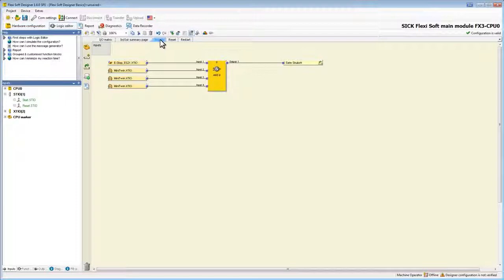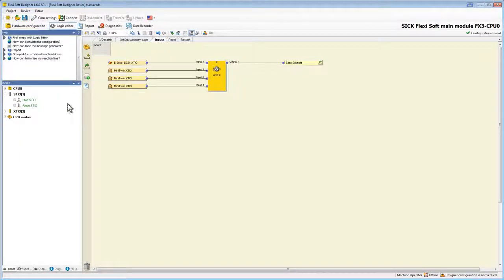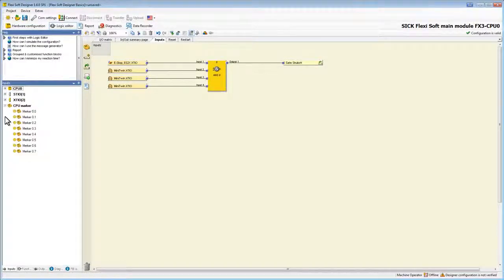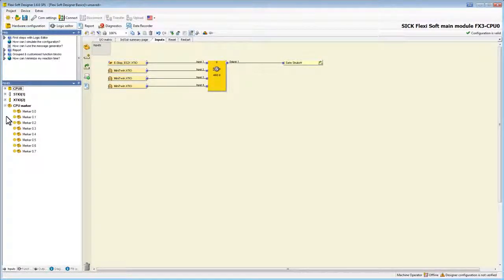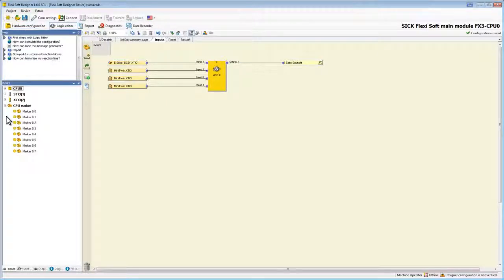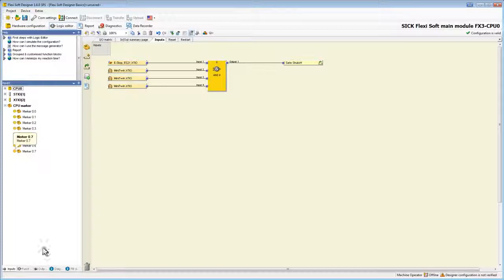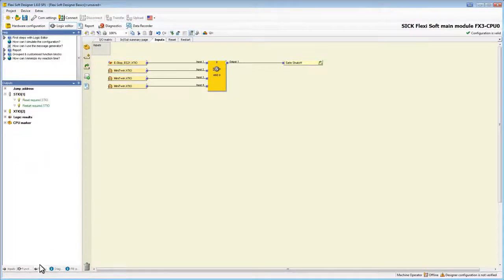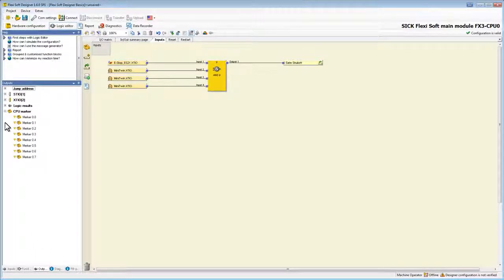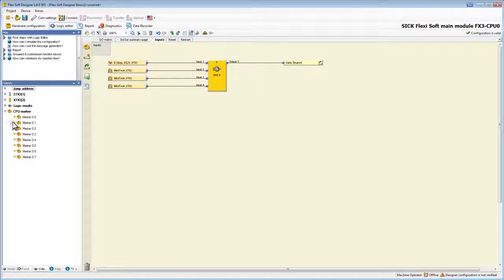The use of CPU markers works basically in the same way as the jump addresses. CPU markers are available as in and outputs here, and contrary to the jump addresses there is always a delay of one logic execution time between the output marker and the input marker. The CPU markers can be considered as variables which are readable and writable. Therefore they are available for gateway routing and other diagnostic purposes.